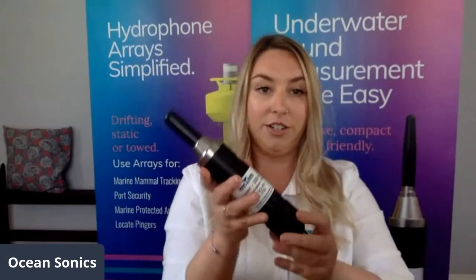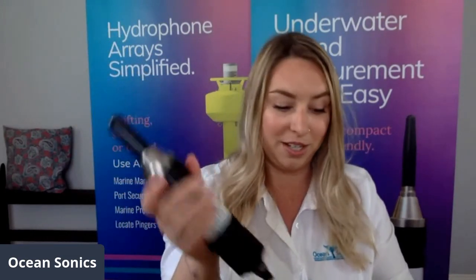So inside every yellow Pelican case, you will find your icListen smart hydrophone. So this, as I mentioned, is 1750. This is the hydrophone that we're going to be using today. It's a basic SC2 model, so it's 200 meter depth rated. And then this is the test cable. As you can see, this is the end that goes into your computer via the Ethernet port. And this can also be used to charge your hydrophone. You can plug it directly into the wall using your power cable.